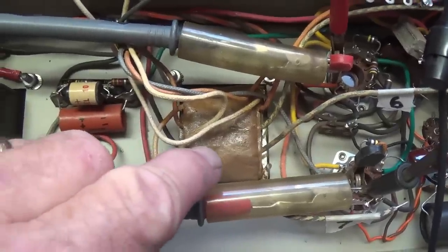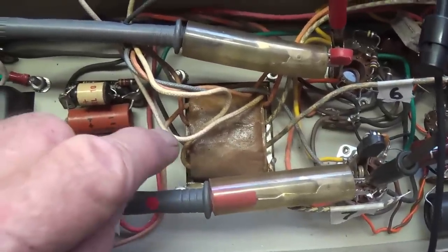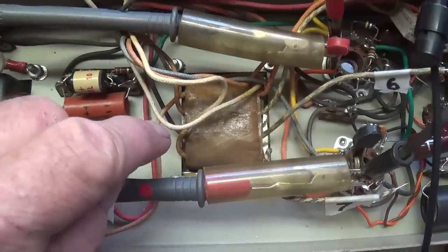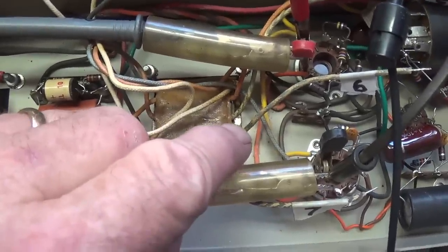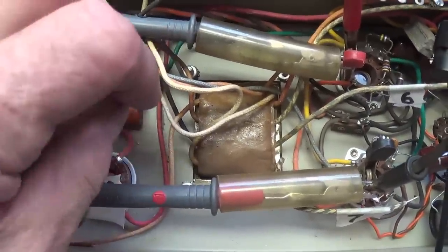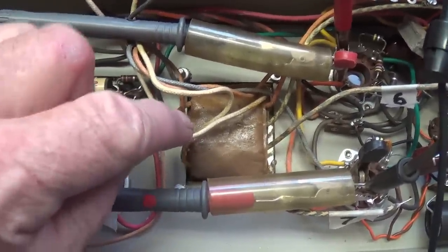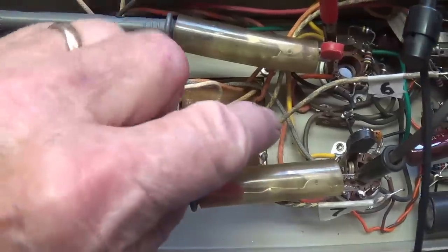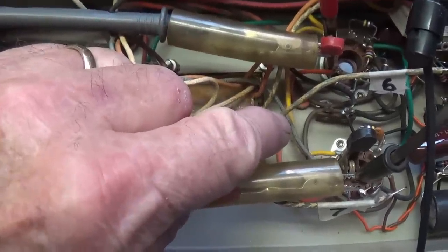So to map this output transformer, remember that the primary side has high voltage, the secondary side has low voltage. I have connected the variac to the primary side, and I'm going to crank in sufficient AC voltage until I get exactly 1 volt out on the secondary.